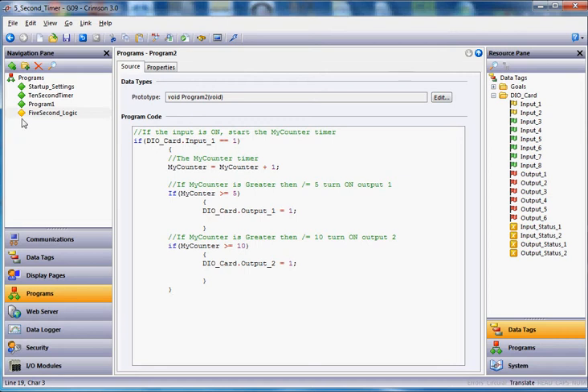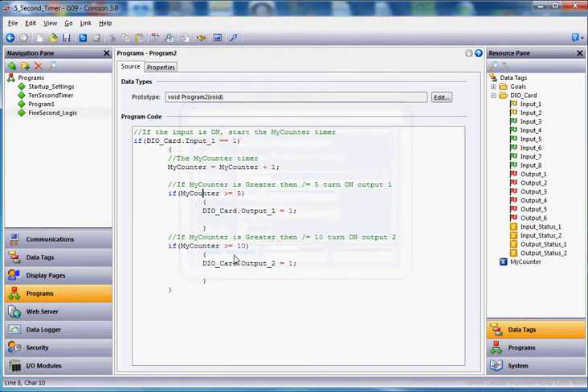So you'll see here, I have not compiled the program, so you see right here, it's a yellow diamond, means I haven't compiled the program. So in Crimson 3, click out here, this button right here, is the translate button. Now we should have a couple problems, or at least one that jumps up. I do not have a value, or a tag called my counter. I can also see right here, that I spelled this one wrong, so I'll fix that real quick here. So I'll go ahead and hit this button here, and let's see what happens. It's going to ask me, do you want to declare a new variable, named my counter? I'm going to say yes, I want it to be an integer tag, because it needs to be more than just a one or zero.